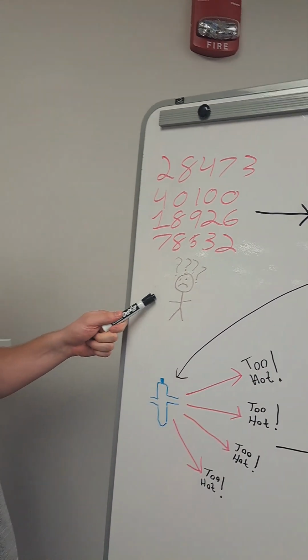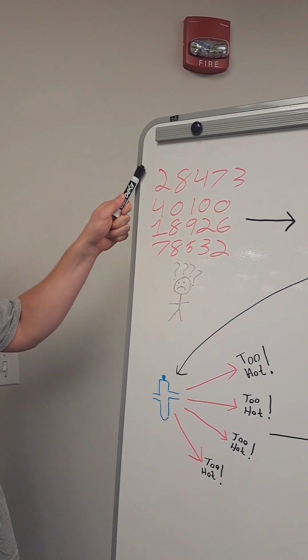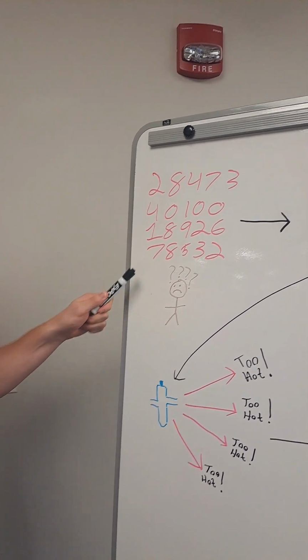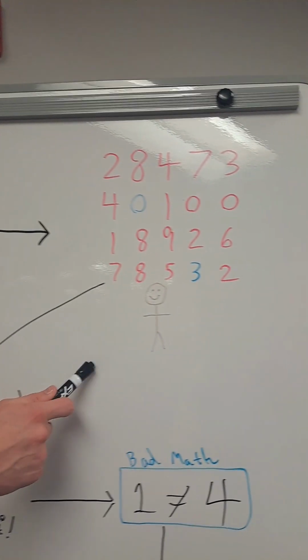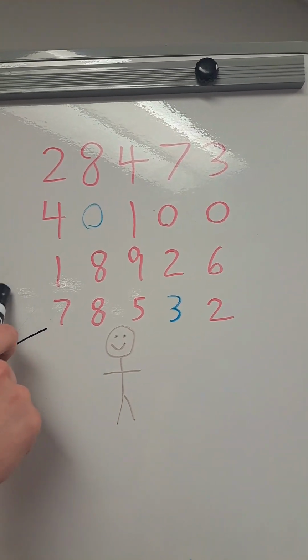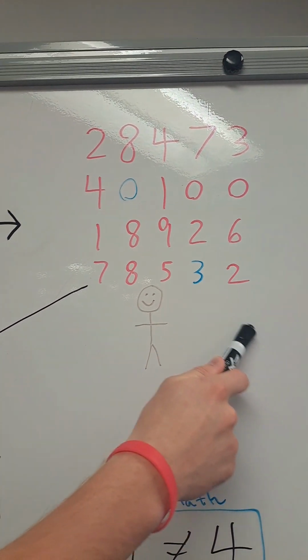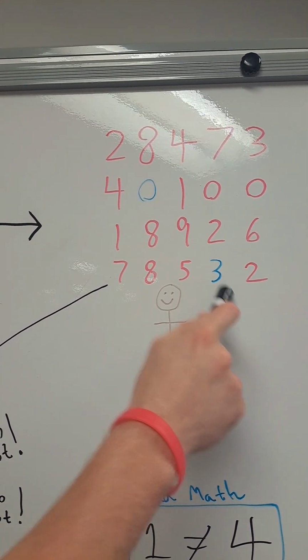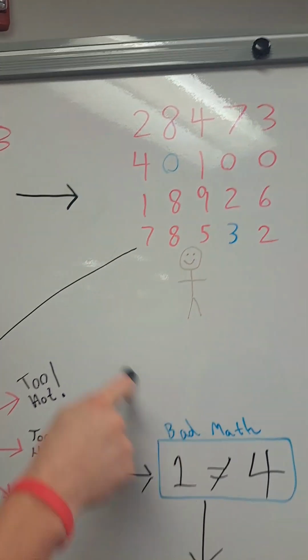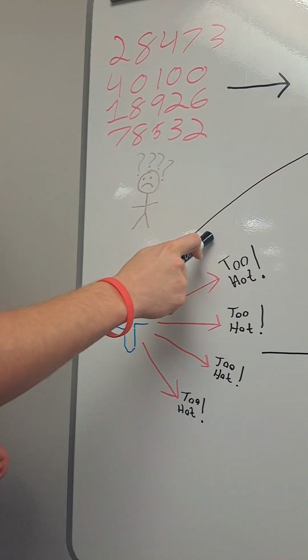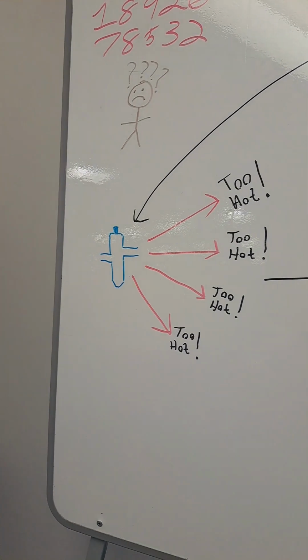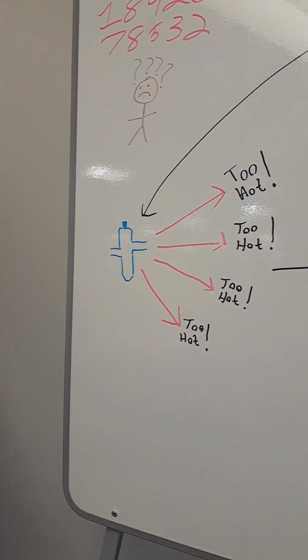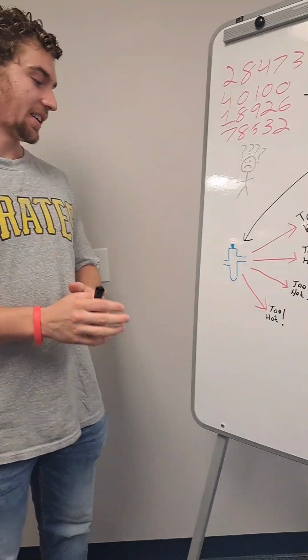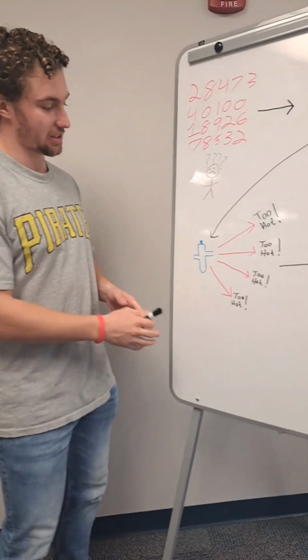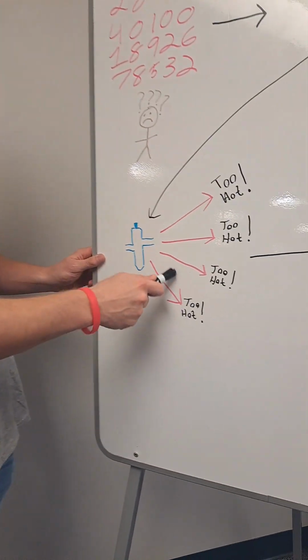See, this guy, he's trying to figure out a problem, but there's all these numbers and he's frustrated. He doesn't know what he's looking at. Then you go over here, and this technician actually has some useful data. He still has all the numbers and the problems, but they highlight the main problems that are causing the rest of these. So this is called a cascade of alarms. An example of a cascade alarm would be a cooling coil valve that is not opening, which is causing the rooms that it is serving to become too hot.